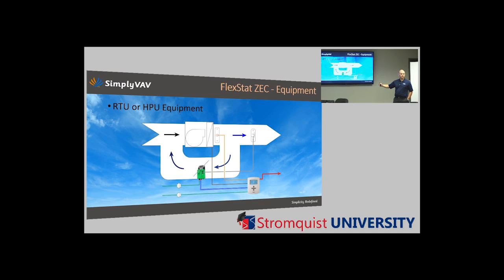Was that just a feedback going to the FlexStat? Yep. From the ZEC standpoint, you can set the set point through the menu. Say you put it at 1 inch, it's going to put out 1 volt and control at an inch of water, and then feed the live signal back to the FlexStat so you can trend it. Okay. And then the actual sensor hooks straight to the controller. Right. But if you didn't have this, then this still has the capability of being configured for whatever pressure you want to maintain on its own.